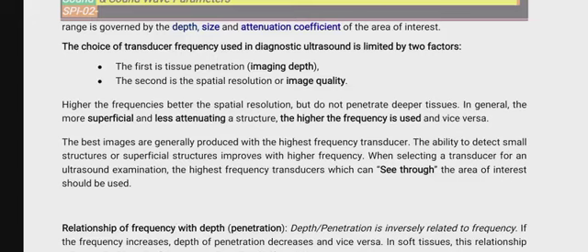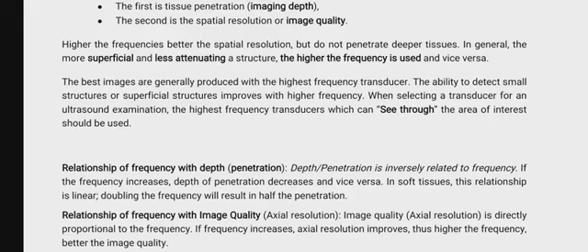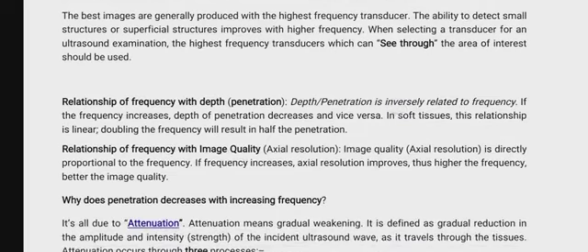So you need to know that higher frequency is better for spatial resolution. If you have higher frequency, your spatial resolution is better, but you will not get to penetrate deeper tissues. So in general, the more superficial and less attenuating the structure, the higher the frequency is used, and vice versa. So if you want to access superficial tissues, use a very high frequency, because there will not be much depth, but the resolution is very high. The best images are generally produced with highest frequency transducers. The ability to detect small structures or superficial structures improves with higher frequency. When selecting a transducer for ultrasound examination, the highest frequency transducer which can see through the area of interest should be used. So it's a trade-off.